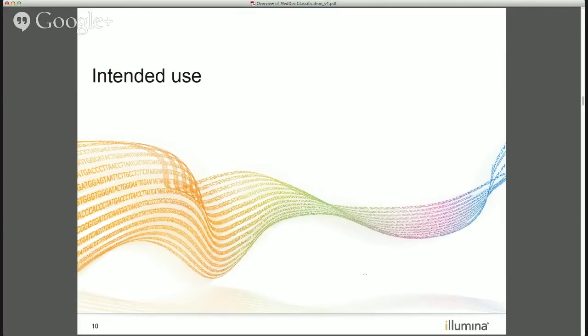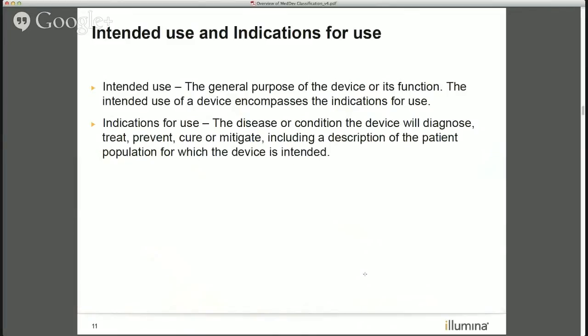Moving on to the intended use section. FDA lays out two definitions — one for intended use and a different one for indications. In reality these two terms are used interchangeably. The point is the intent and the words you put in there: the general purpose of the device and its function, the disease or condition, the diagnosis, the way the device is going to be used — that is the information FDA is looking at when determining how your device classification is going to fall and how it plays into risk.